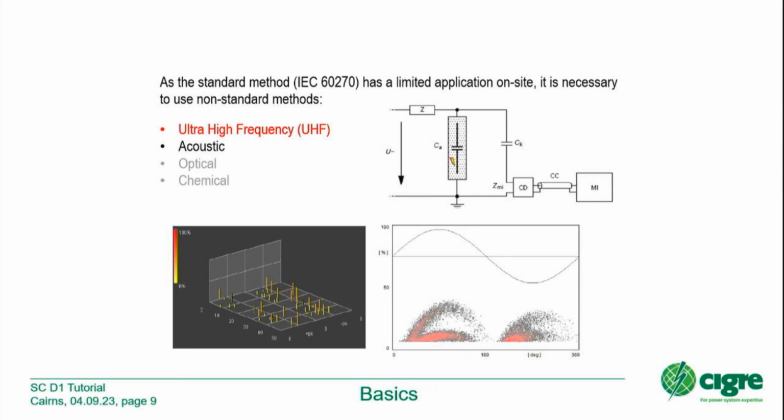You mentioned in the presentation, and as is in TB 654, the importance of the same test: the same injection pulse generator, the same couplers, and the same or better measuring device. We have some challenges in discussing with the manufacturer, without using what they recommend, being able to access a measuring device of the same make and model. How can we investigate or convince or argue with the manufacturer that alternative measuring devices are equivalent or better?